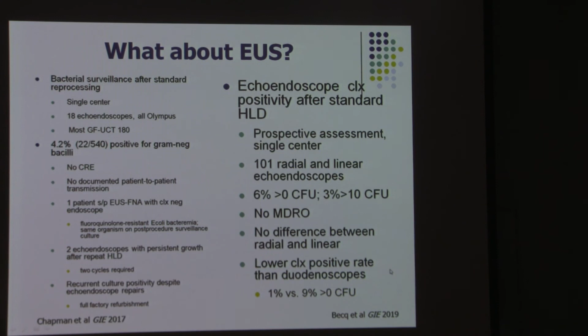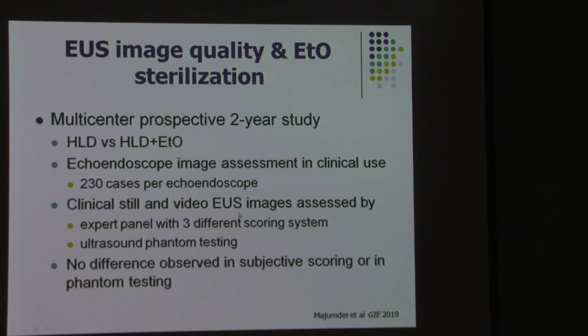The good news is that if you are considering using gas sterilization, there is, I believe so far in abstract form, a multi-center 2-year study of high-level disinfection versus high-level disinfection plus gas sterilization, addressing the concern of whether the echoendoscope image would be affected with the use of gas sterilization. But so far, it does not appear to be the case.